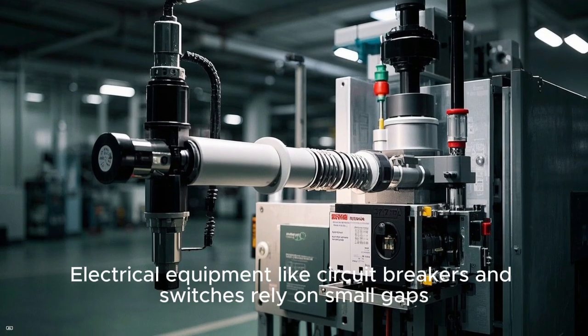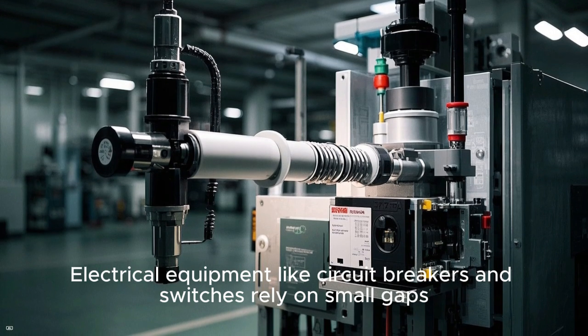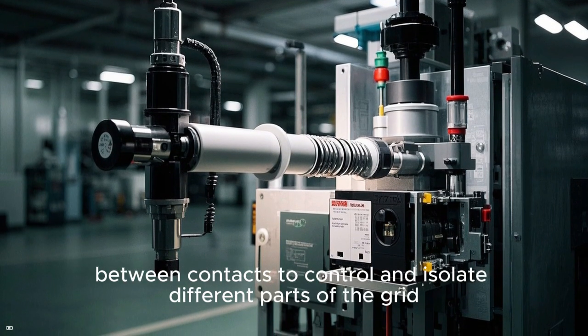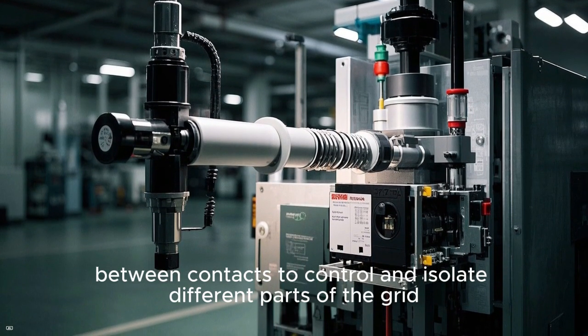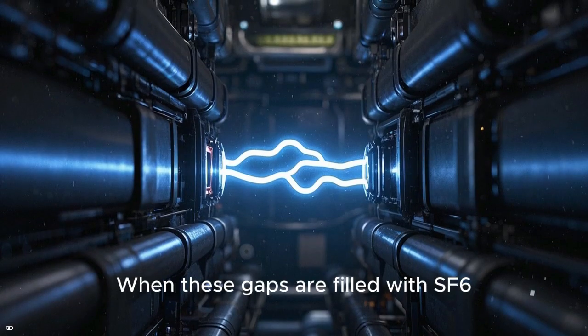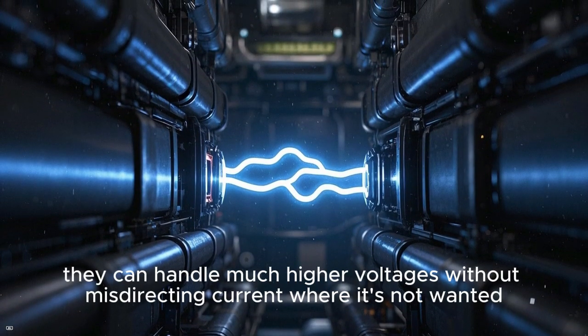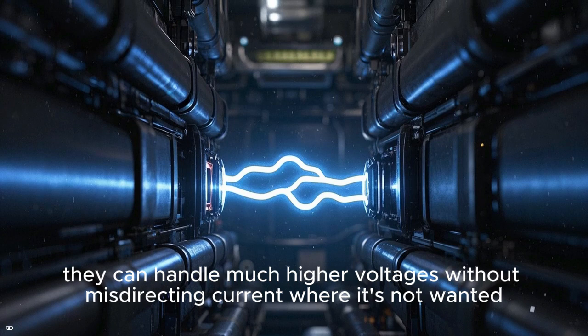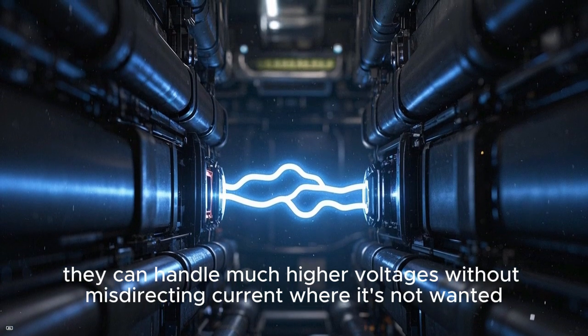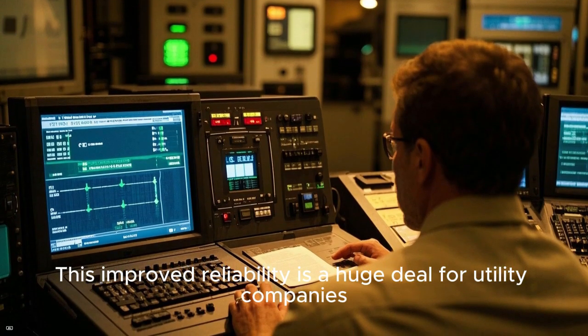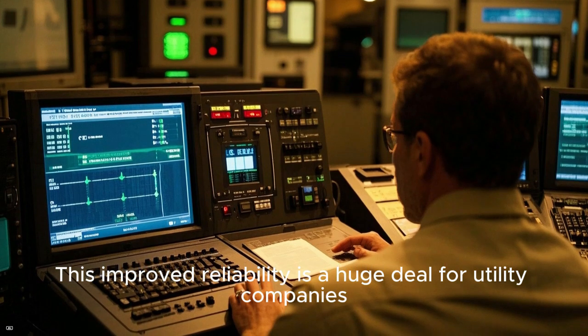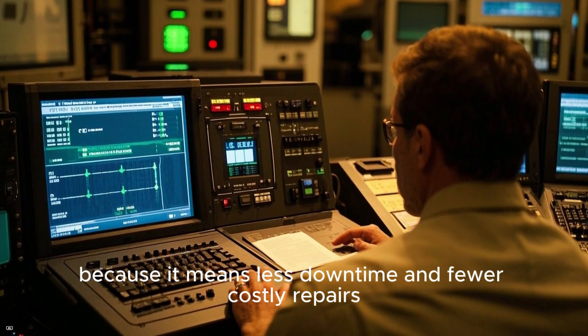Electrical equipment like circuit breakers and switches rely on small gaps between contacts to control and isolate different parts of the grid. When these gaps are filled with SF₆, they can handle much higher voltages without misdirecting current where it's not wanted. This improved reliability is a huge deal for utility companies because it means less downtime and fewer costly repairs.